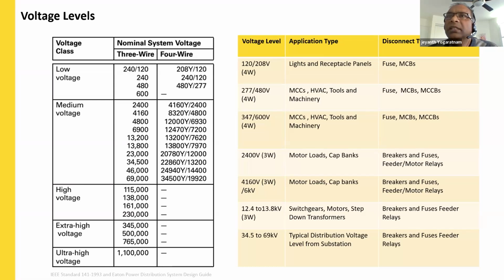When it comes to medium voltage circuits, typically those circuits are protected using circuit breakers and dedicated protection devices. If it is a transformer, there will be a transformer protection relay, motor protection relay, or feeder protection relay to provide intelligent decision making based on the power system conditions. As disconnecting devices, breakers and air circuit breakers are commonly used. But in some instances, short circuit protection can be provided using fuses as well. When it comes to the 34 kV and 69 kV voltage levels, those are more or less involved with the substation level.